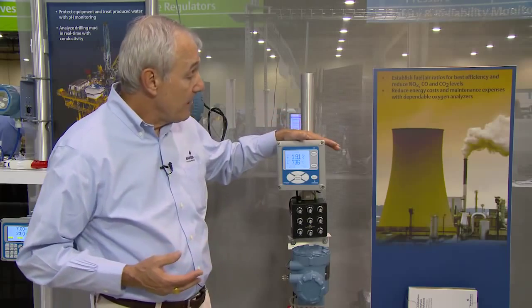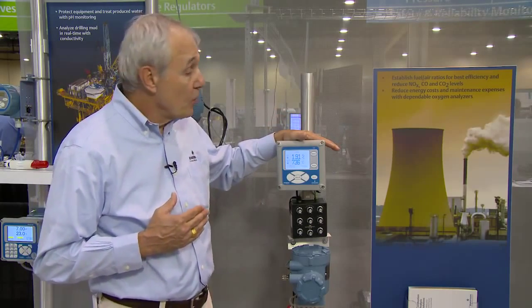that may be dangerous. Finally, this analyzer offers a stoichiometric feature, which permits an operator to know when he's gone into reducing conditions. Instead of just going to zero and stabilizing at zero, this analyzer can actually record readings below zero so that the operator knows that he is actually in reducing conditions.